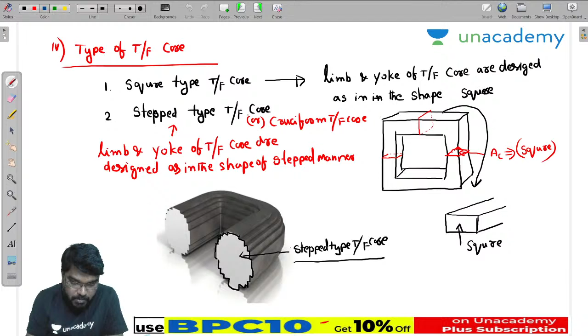So here, types of cores: square type transformer core and step type transformer core. The limb and yoke are designed in the shape of a square, meaning the cross-sectional area of the core is square. In the other type, the cross-sectional area is in a stepped manner, so this is known as the step type transformer core or cruciform transformer core.